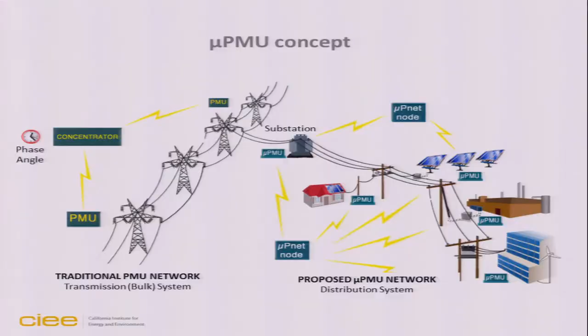No one has done this on distribution systems, first of all, for the reason I mentioned, which is that the measurements are more challenging. You have to look much more carefully than at the transmission system if you want to get useful information out of voltage angle. There is a difficulty in making the business case for installing a measuring device at the distribution level when you only have so many customers that are really affected by the part of the circuit that you're measuring there. Much easier to make the case to spend a couple tens of thousands of dollars for a transmission level PMU. Much more difficult to make that at the distribution level. So you need a less expensive instrument, but one that's more accurate. Now, the main thing, though, is that historically there was no need for measuring voltage angle at the distribution level. There wasn't even really a need to measure voltage magnitude in real time because, as I said, things used to be simple and straightforward. This is now, as we all know, changing.